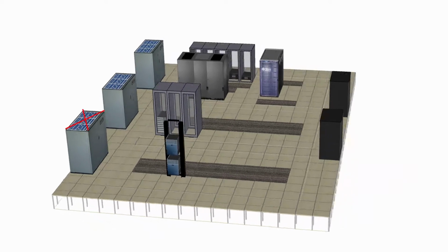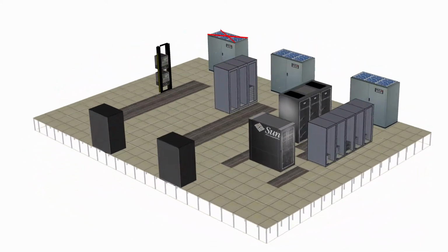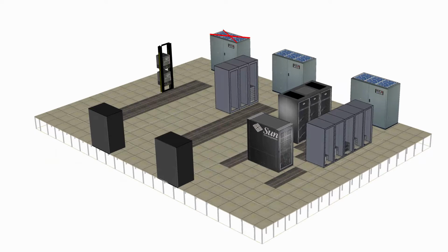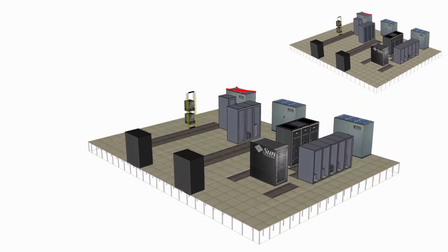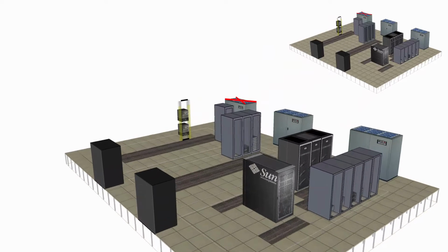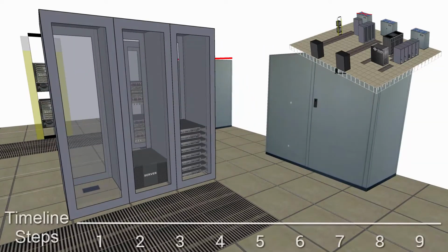The idea is to use historical trends collected from their monitoring equipment to make the impact of future changes a bit less unexpected. In this video, we're examining a sample data center designed with N+1 redundancy and equipped with a full monitoring and DCIM kit. Starting at 20% of the design IT load, we're going to simulate a series of IT deployments.